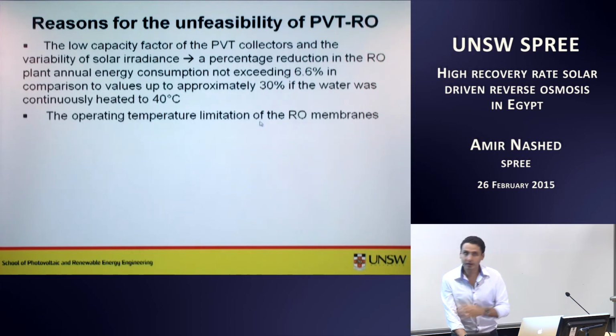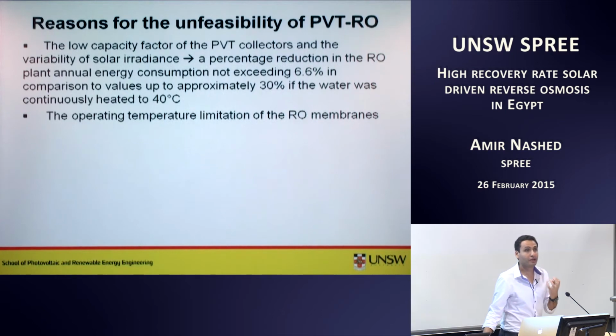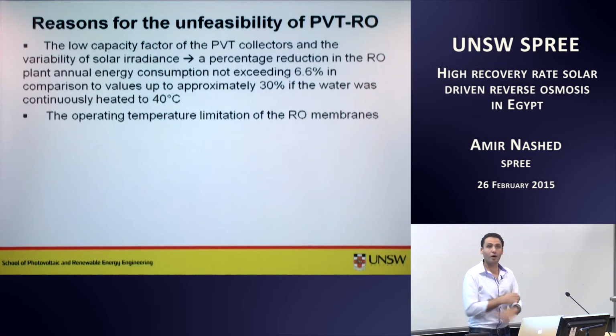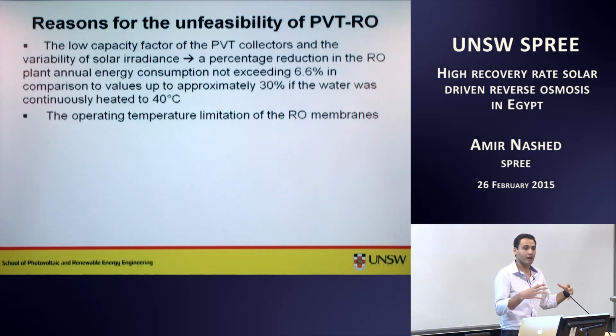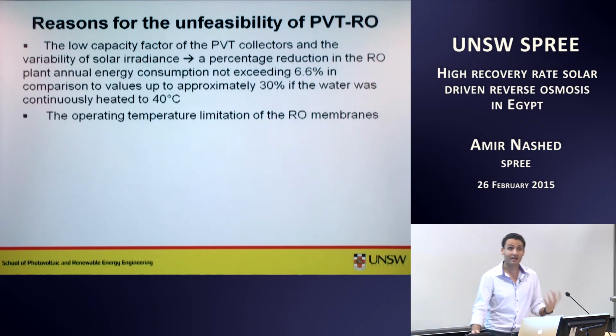Secondly, there is the operation temperature limitation of our plant. So you cannot just say, okay, I will use a huge PVT collector area to increase the temperature, because you will exceed the maximum temperature of the RO modules. And in my design, it will mean that a section of the PVT collectors will work under stagnant conditions for a longer time, and it will actually decrease the yield.